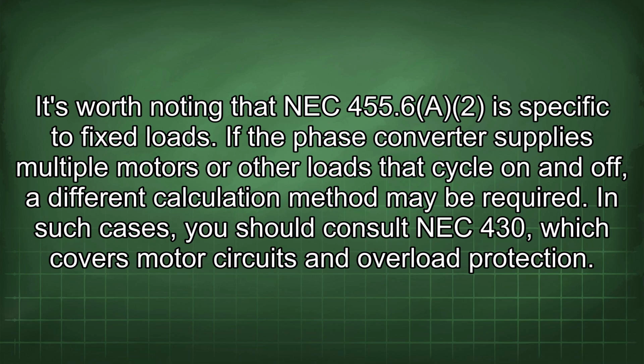It's worth noting that NEC 455.6(A)(2) is specific to fixed loads. If the phase converter supplies multiple motors or other loads that cycle on and off, a different calculation method may be required. In such cases, you should consult NEC 430, which covers motor circuits and overload protection.